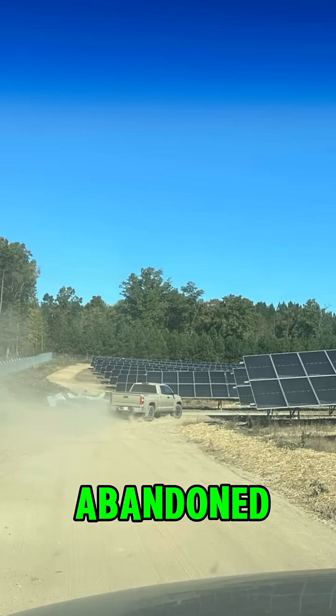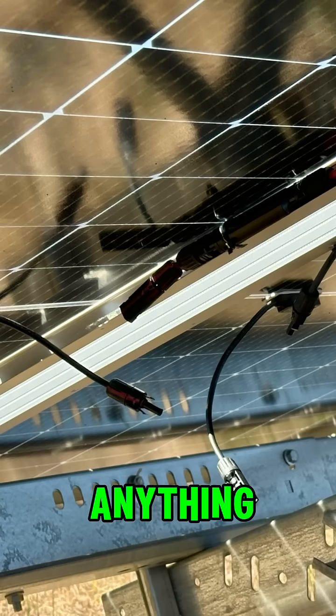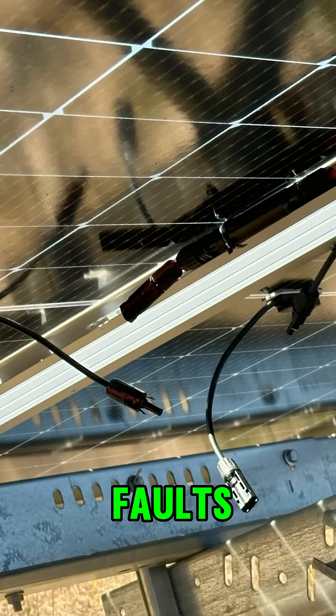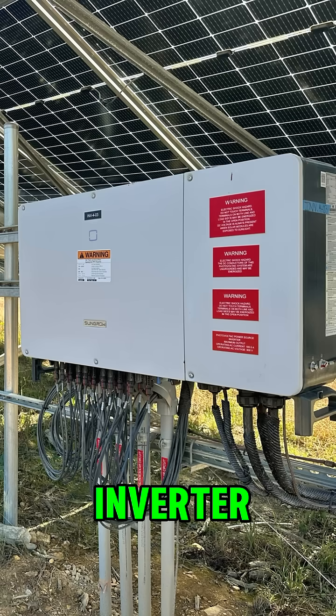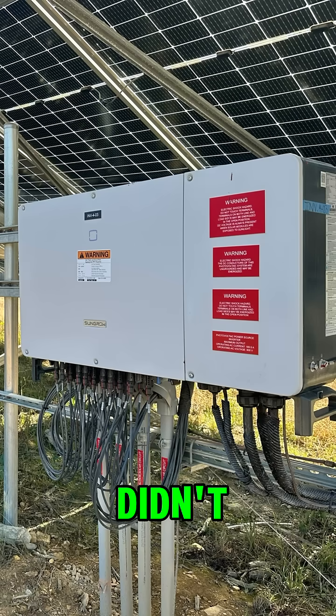The BBQ was abandoned as we all headed out to investigate. We couldn't see anything visibly wrong — no bad connections, no grounding faults. Then we moved to the inverter. We cut the power using the breaker and AC disconnect switch, but strangely the inverter didn't shut off.